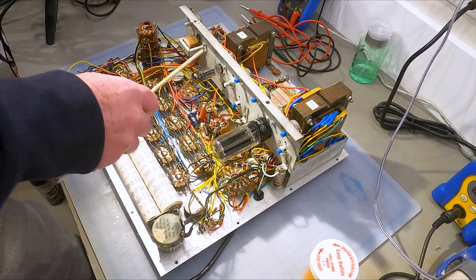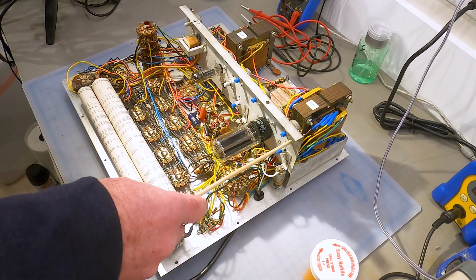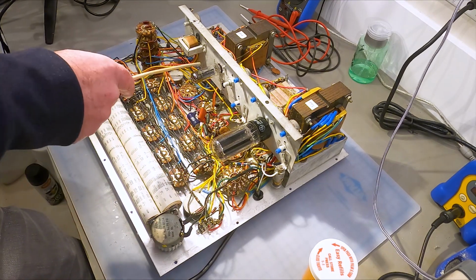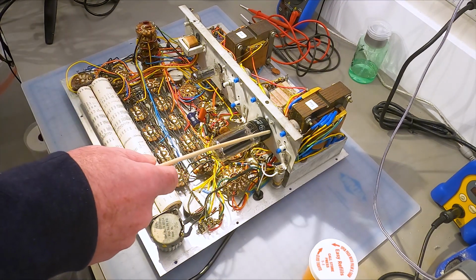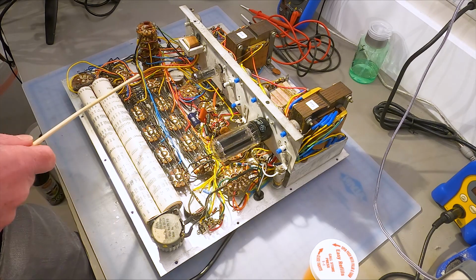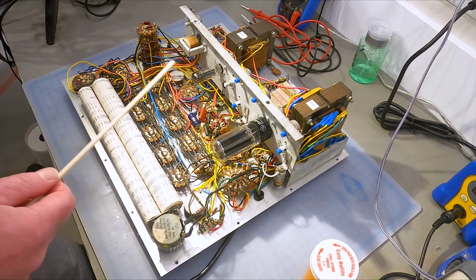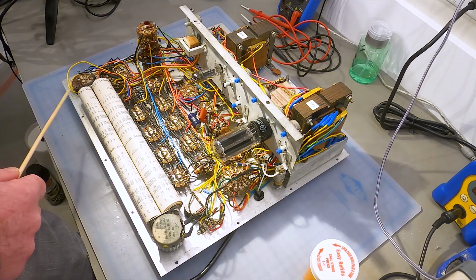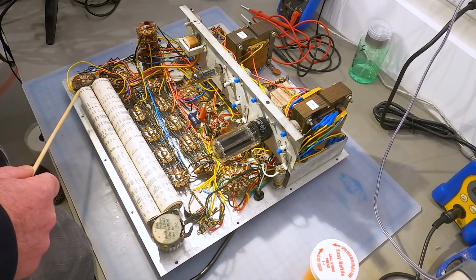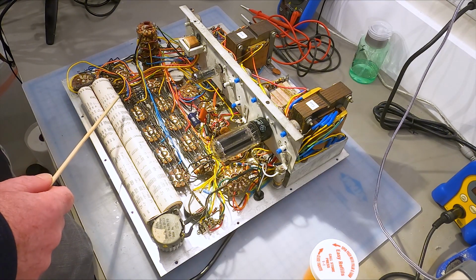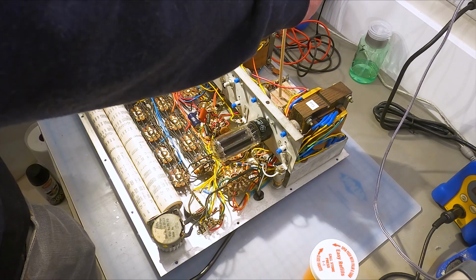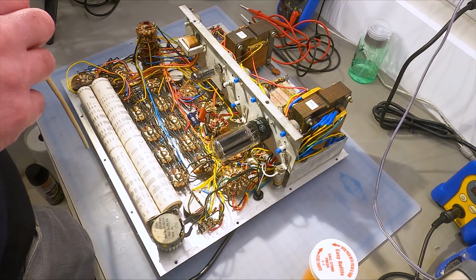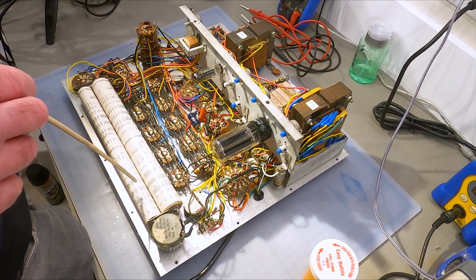There are a number of calibration potentiometers on this section. This is the so-called power supply section of this instrument, and that's really mostly what it is, the power supply and some elaborate switching and then some metering capability. The meter itself is below here. There's another capacitor across that meter, and we'll check that one out as well.